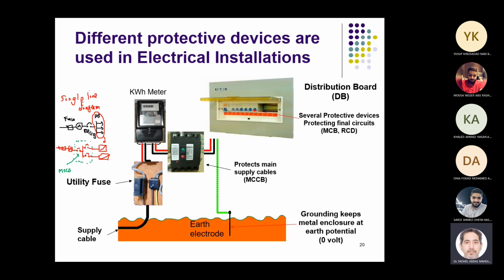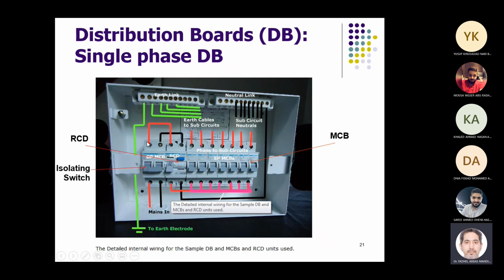In MCBs and DBs, you can see them inside a distribution board. So the arrangement in a house, for example: supply comes to fuses, then to a meter, then to a main breaker, which in our houses is an MCCB. This then feeds a panel, a distribution board, as we call it, in which we have different types of protective devices. These ones are the miniature circuit breakers. But in addition, we have another device. The miniature circuit breaker provides overcurrent protection, but for shock protection we have another device called the residual current device, RCD, which acts like a differential protection device, comparing the currents in the line and neutral. If there's a difference, it trips the circuit.